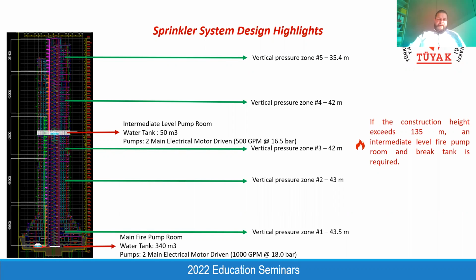That's why if you have more than 3 vertical pressure zones, it means your building is higher than 135 meters. You need to provide an additional intermediate technical floor in your building. For example, this is a project from Uzbekistan. The building is more than 200 meters.